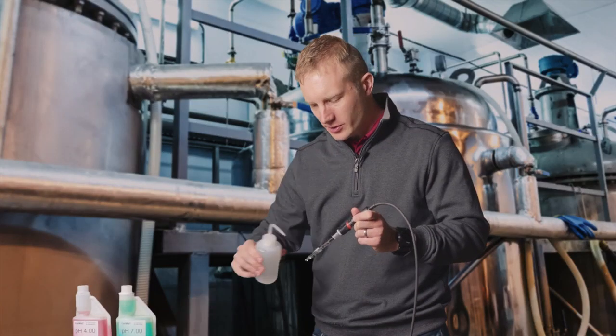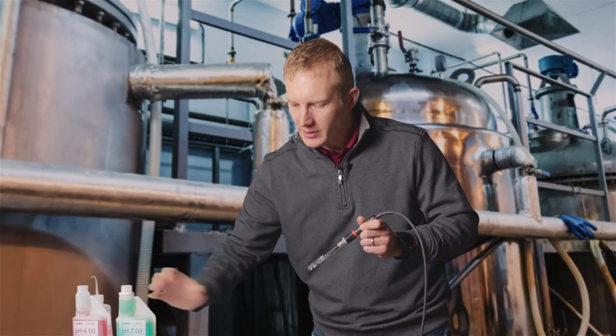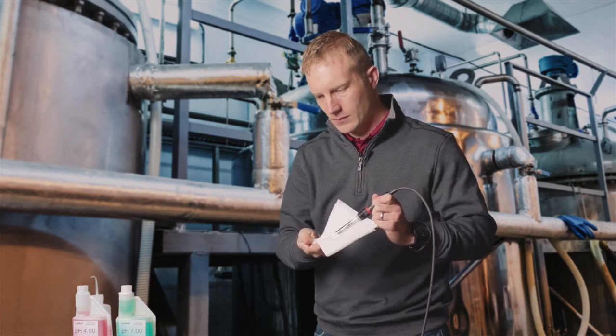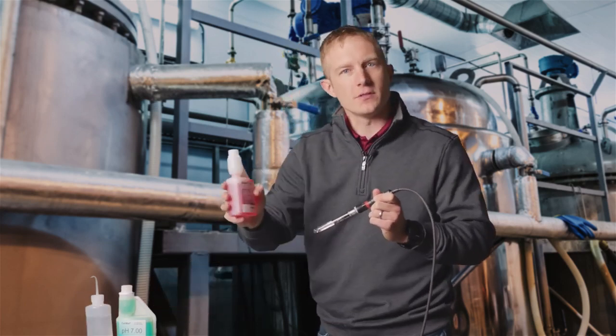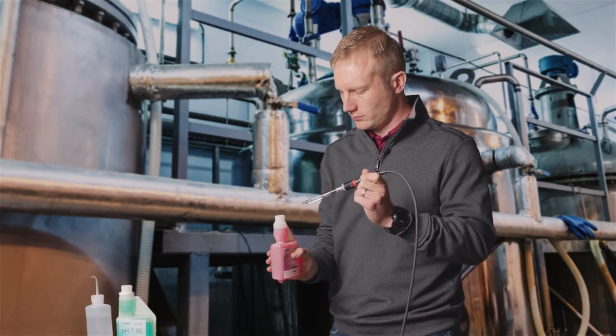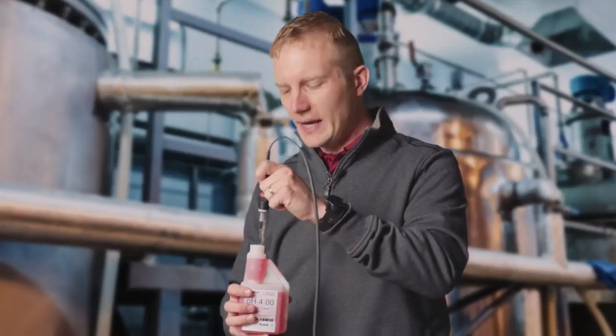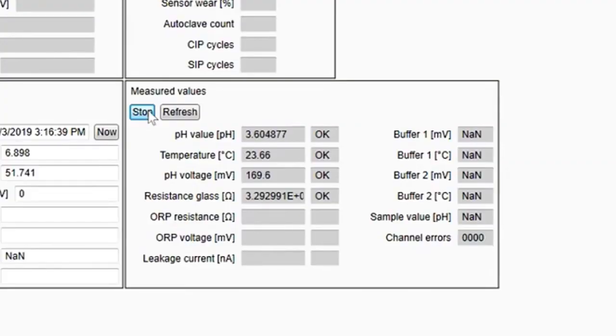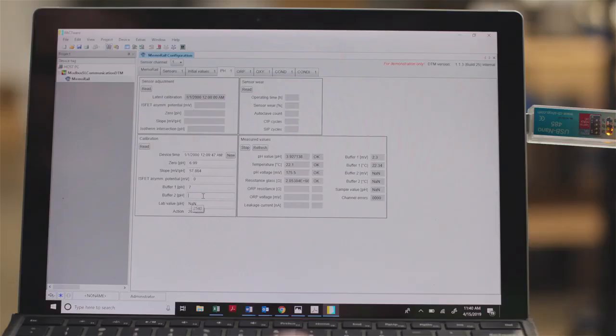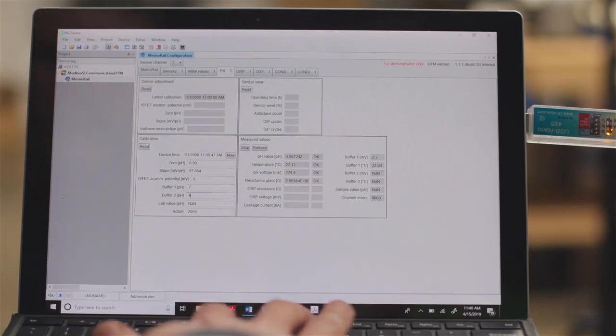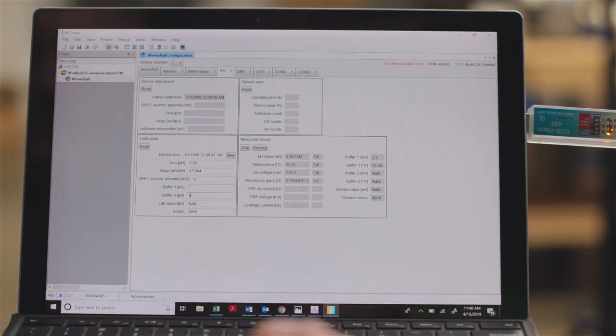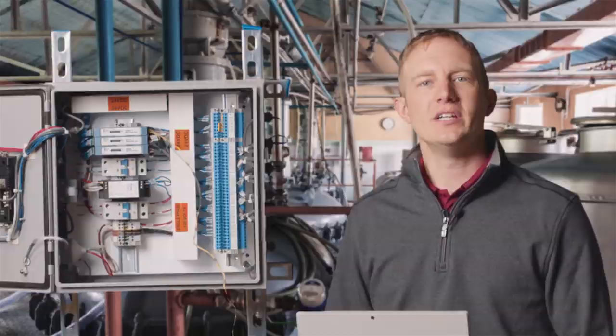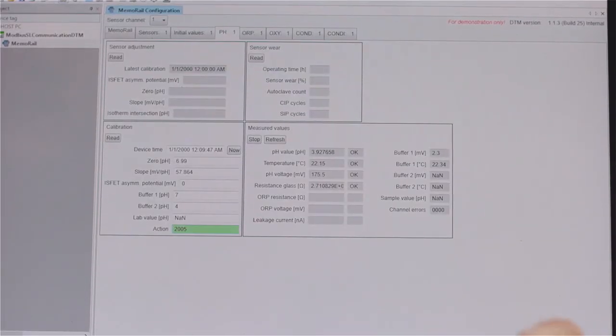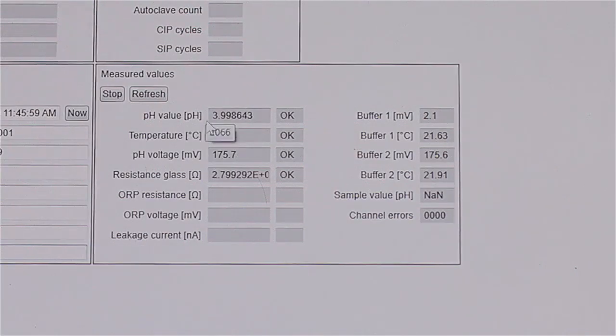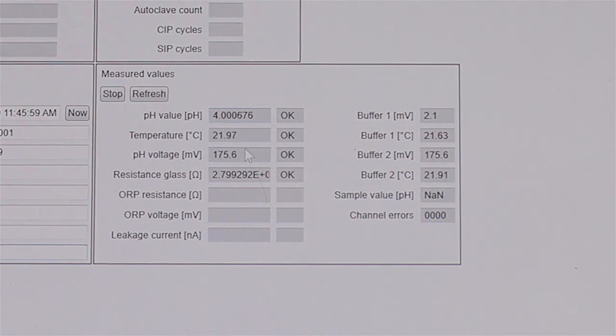We'll now rinse our sensor again, dab it dry, and place it in our second buffer solution. Stir lightly and let your measured value stabilize. Now write the temperature compensated value of the second buffer in register 2540 and press enter. We will finalize our calibration by writing action code 2005 in register 800 and monitoring our measured values.